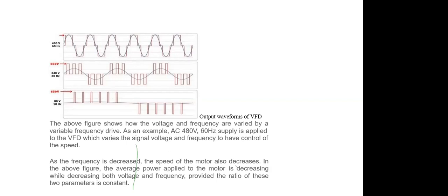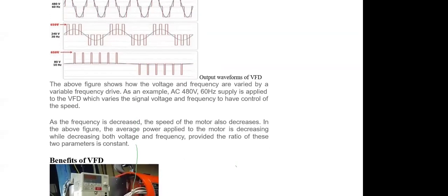And after this is done, again through a component called IGBT, insulated gate bipolar transistor, which is the most commonly used, it is again converting this reduced frequency, or this reduced DC, to AC. And after reduction, if it is 40 cycles per second, for example, then these 40 cycles are applied to the motor. Ultimately, as the frequency is less now, the motor RPM is also less.